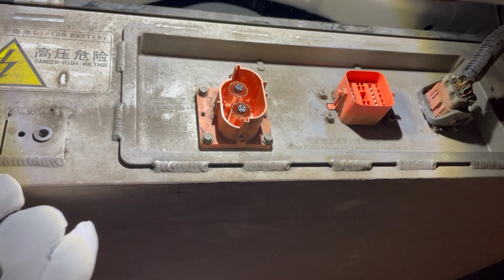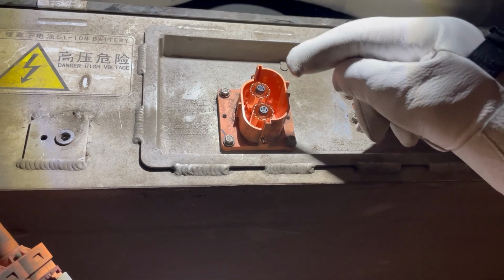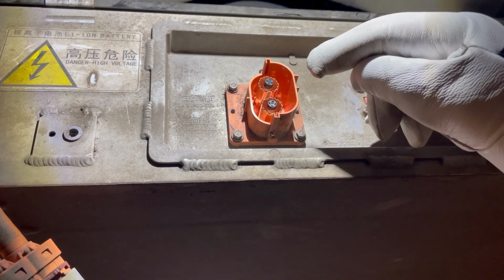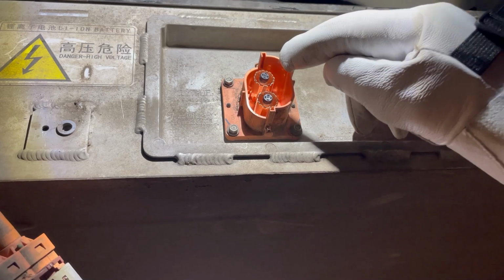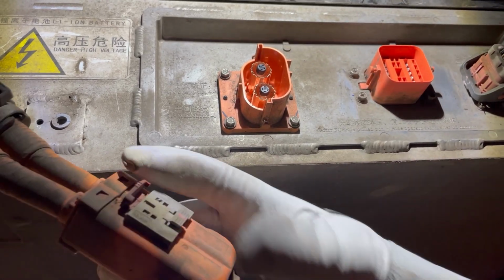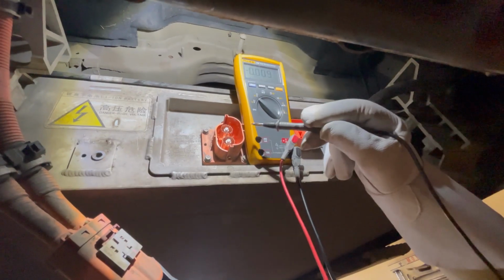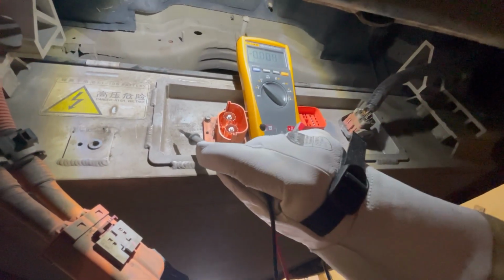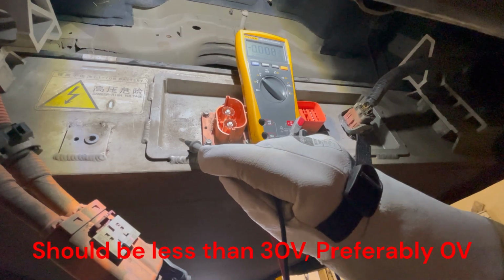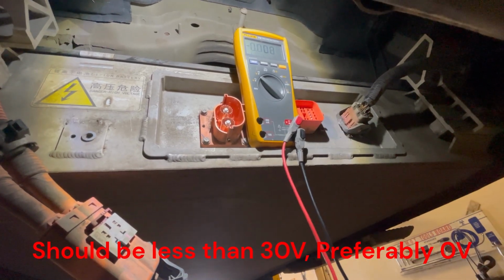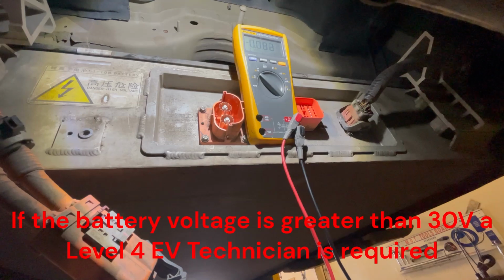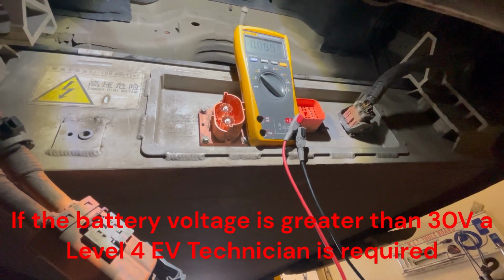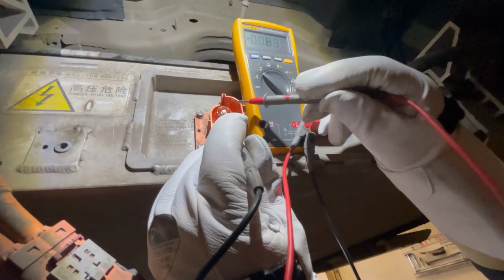There we go. And you can see there's the two main high voltage terminals, positive and negative, coming out of that battery. So that's where we're going to check for absence of voltage. We can also check on the way back that there's nothing coming back from the inverter and the two main terminals there. So here's the two main contactors here. You can see actually it says high voltage main circuit plus, high voltage main circuit negative. So we've already checked the multimeter on the proving unit, we know that it works. We're going to check across the two terminals, see what we have.